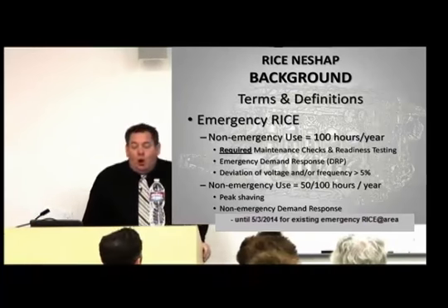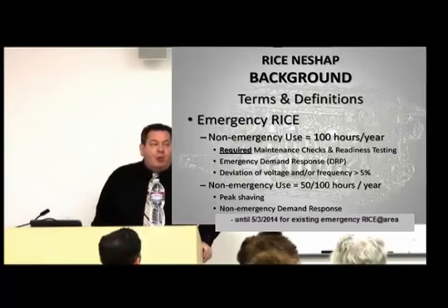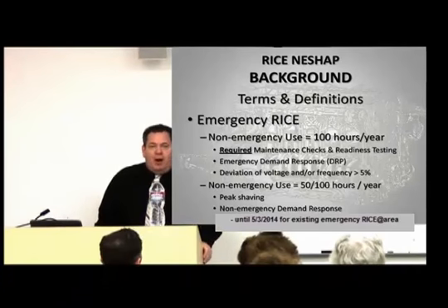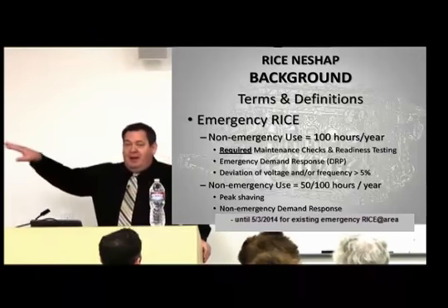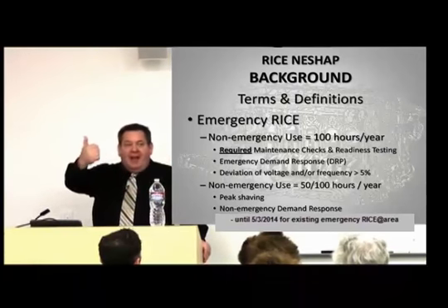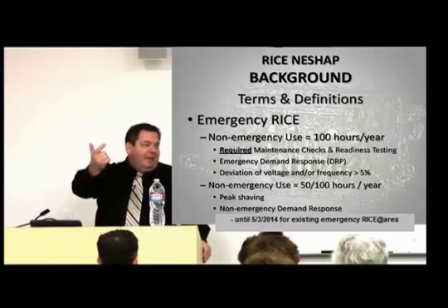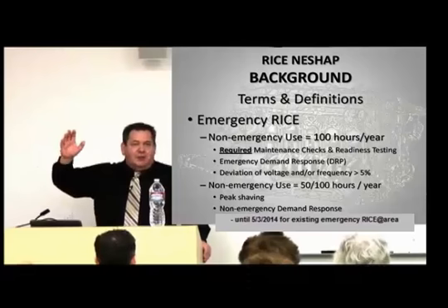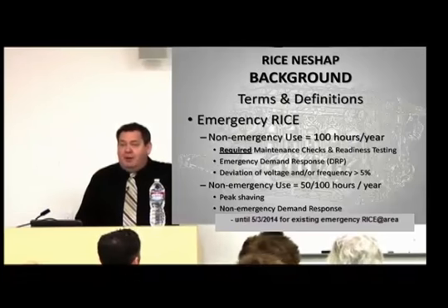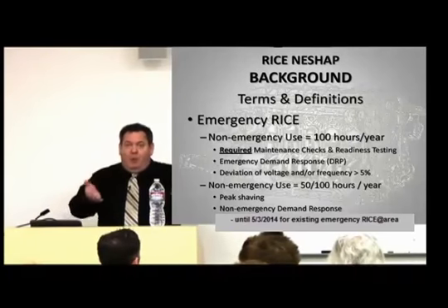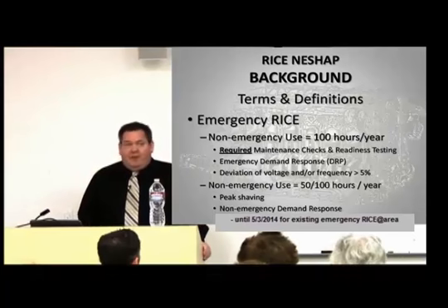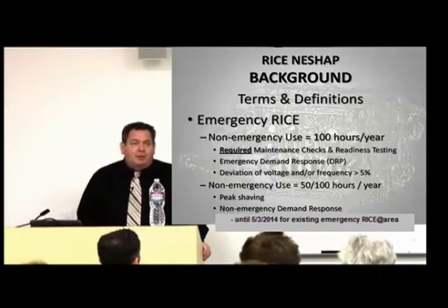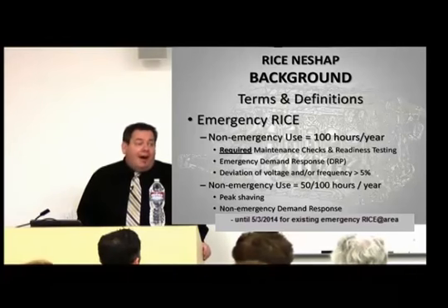Reason number one, required maintenance checks and readiness testing. And the reason required is bolded and underlined is because required means required by somebody else other than you, meaning the engine manufacturer, the equipment manufacturer, if it's an emergency generator, the generator manufacturer, if it's an emergency pump, the pump manufacturer, maybe the system operator. So if you're part of some type of system and they want to tell you to check for readiness, you have to abide by their requirements for running the engine. So for maintenance checks and readiness testing, required.